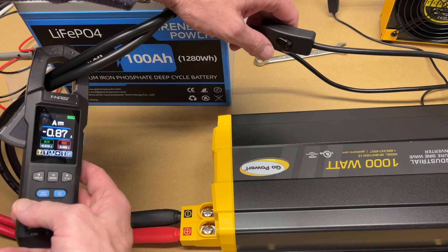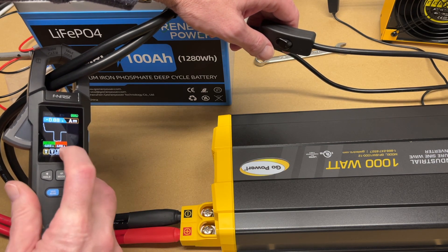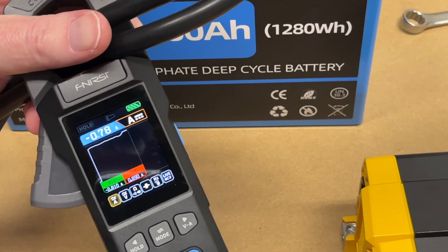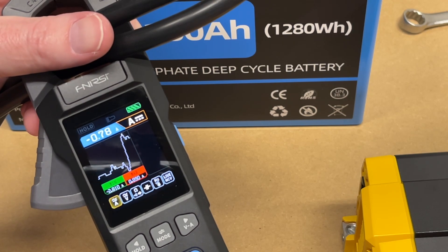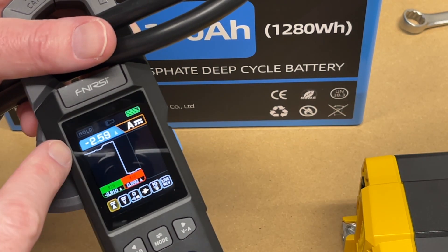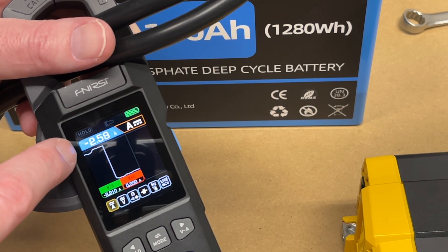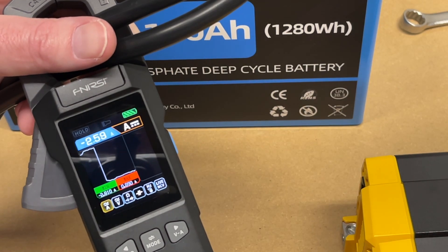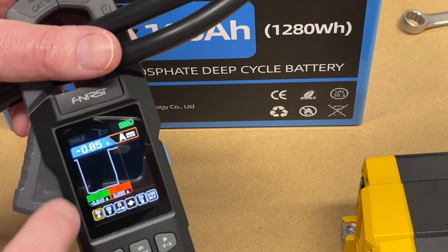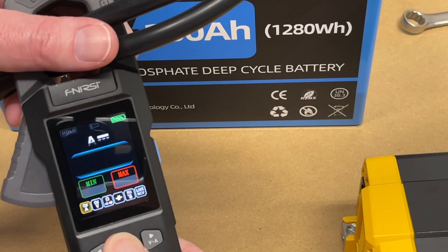Turning the fan off, we can view the data as a graph by holding down the mode button. The graph shows the readings over time — we can see we're at 0.77 amps at idle. Turning the fan back on shows 2.59 amps, and we can see it spike high on the graph. This is useful for catching startup surges. Hold mode again to go back to the normal display.